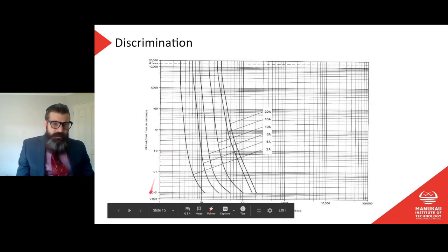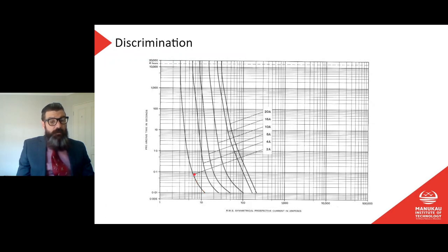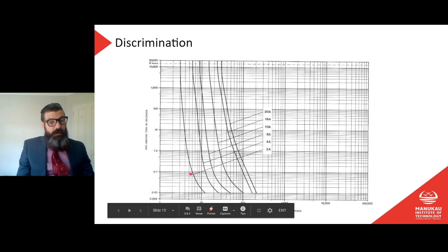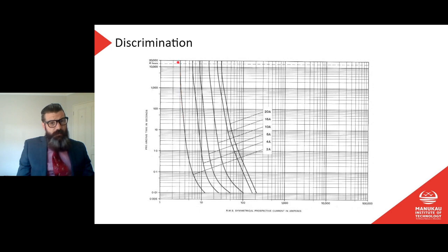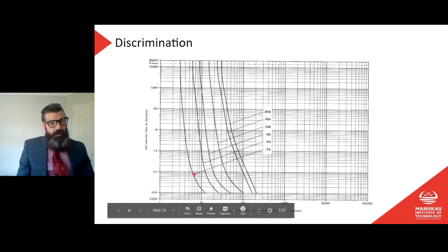So as this is our pre-arcing time in seconds, so that's our time, and then this bottom one is going to be our current. So as you can see there, as the current increases as we go left to right, particularly around this area here, if we're looking at the 2 amp, then the total time for that device to break, or the pre-arcing time rather, goes down. And in fact, from here to say here, that's a relatively small increase in current, but a large drop in time, right?